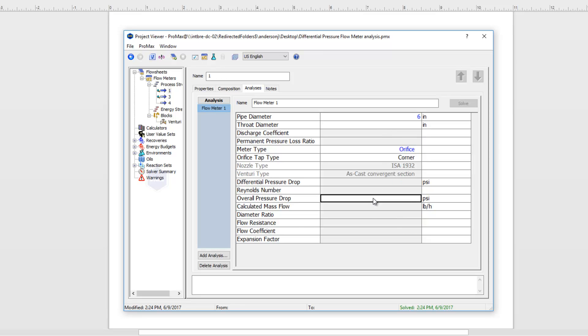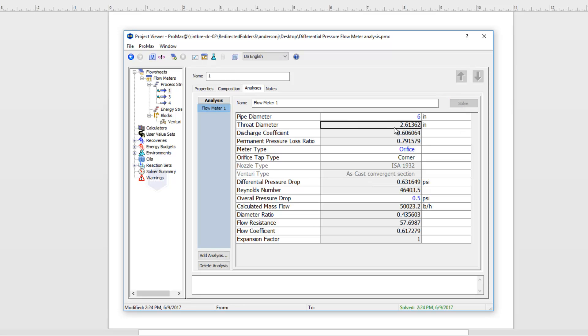In that case I would get rid of my throat diameter and instead I could type in the overall pressure drop that's acceptable. I'm just going to say half a pound here. Once I have a pressure drop specified I can again solve and it will calculate what throat diameter would be required and again gives me my other bits of information.